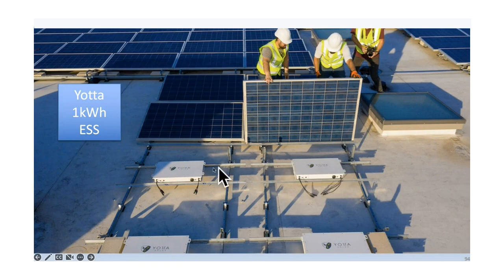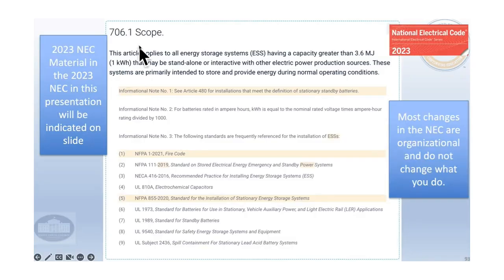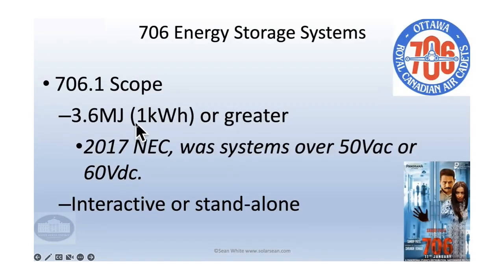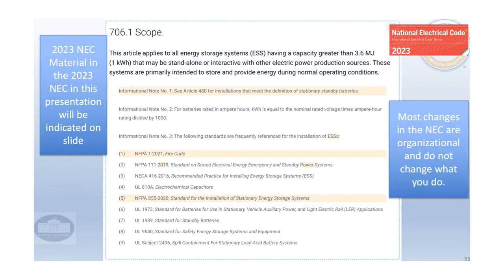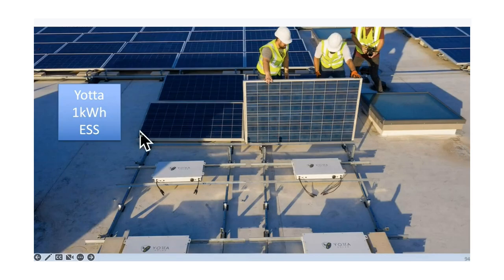They even told me that they have a cooling system. It's kind of interesting that it's 1 kilowatt hour. It barely fits into the scope of 706, which is 1 kilowatt hour for the 2020 NEC and 2023 NEC. And I was like, well, shoot, you could have made it just 1 watt hour less, and then you wouldn't have to follow that many rules.